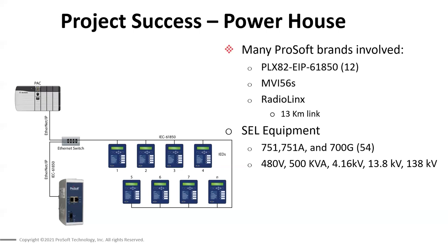On whether any module in the MVI series is coming to fit in the ControlLogix rack for IEC 61850: yes, that new MVI56E-61850C module is exactly that. On whether improvements will be rolled over to existing modules: it will not be rolled over to the PLX82s — unfortunately that hardware doesn't support things like PRP and time synchronization. However, as we release newer, more powerful gateway modules — which is something on our roadmap — we will look to add IEC 61850 support with these new features. More to come on that, probably sometime next year.